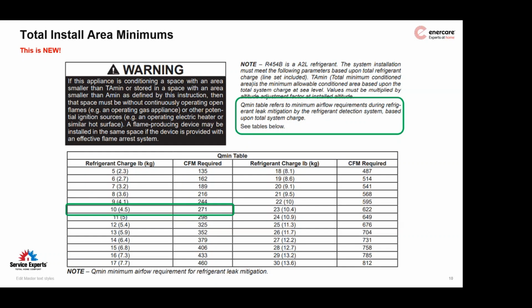There is a sensor in the coil, or on the coil, that will sense a small amount of refrigerant, actually about 1% of the total concentration in the air. At about 1%, Lennox will turn on their dilution or mitigation process. The board will bring on the fan and shut off all the heating sources and cooling sources. But there is a required minimum of 271 CFM for 10 pounds of refrigerant. And you can see on that chart there are a series of different refrigerant weights and how much CFM is required to be moved if there is a leak.